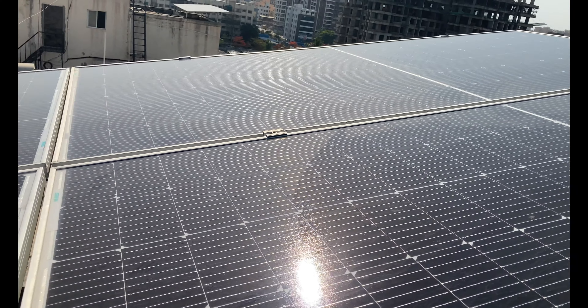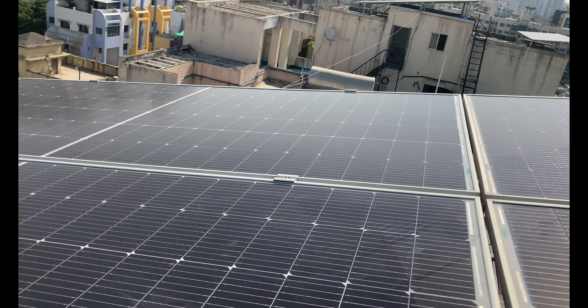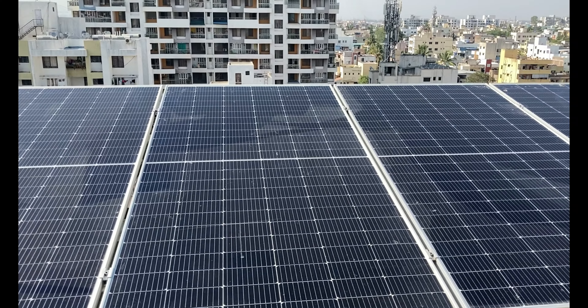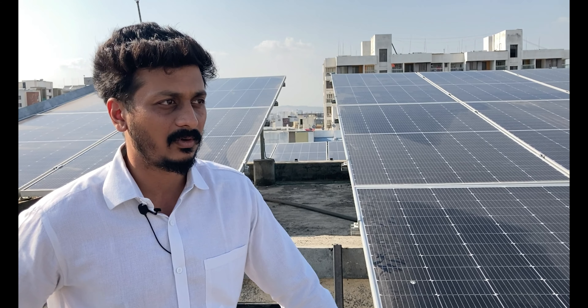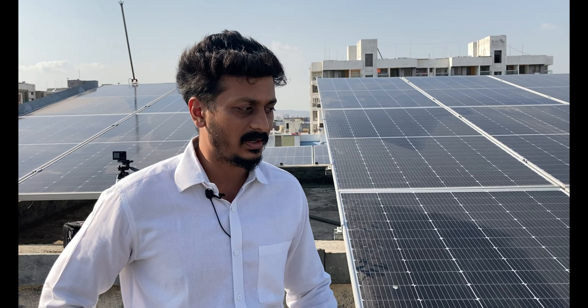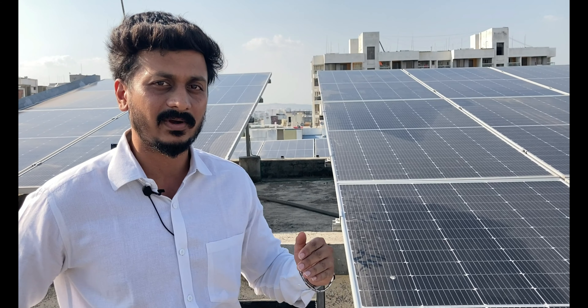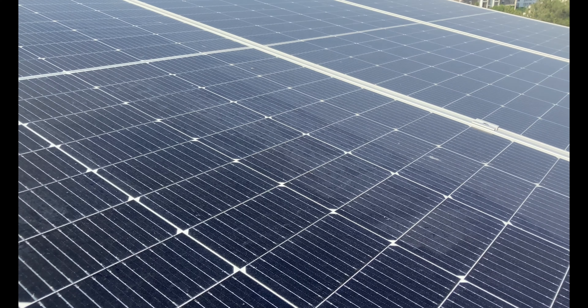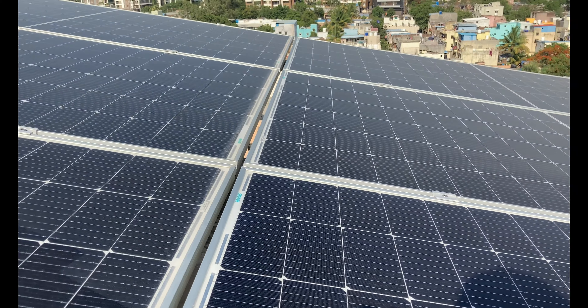We have installed 36 monocrystalline panels of Waaree over here because we are space-constrained. They come with a 10-year manufacturer warranty and a performance life of over 25 years. At the start the panels give 100% efficiency, and at the end of 25 years they will still give about 80 to 85% efficiency. Their efficiency is about 19 to 22%, so we can install more capacity in less space — that's why we have gone for that.